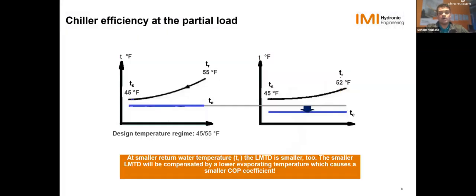And when you look at chillers, what happens is, if the chiller is designed for 45 and 55 degrees for your return, then as your return temperature lowers from 55 down to 52, the evaporating temperature of your refrigerant lowers automatically, which then will lower the overall efficiency of the chiller. And that's what we want to avoid. We do not want to see that lowering of the coefficient of performance in our chillers.